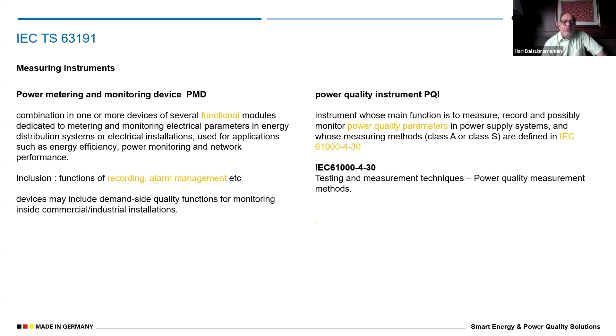So what happens here is they've divided this into PMD2, PMD3, PQIS, and PQIA. This is a very important table specifying what these meters should measure at minimum to be called PMD2, PMD3, PQIS, or PQIA. Each meter has to be appropriately matched to where the users, zones, and major sites are. Site is predominantly a factory, and their incoming is called a site, which is defined here. These are the 6 phases.